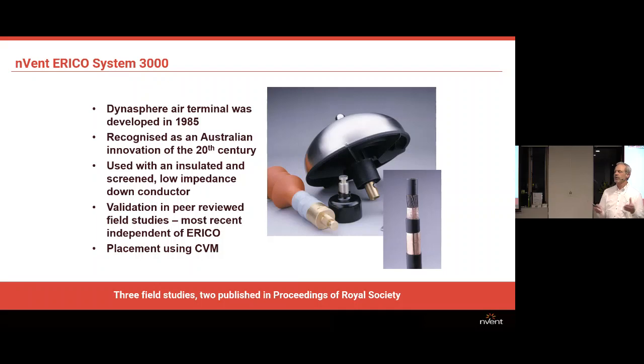The other active system is the one that has been going in for many, many years, ever since I've been representing Erico and GLT, and that's the System 3000 with the Dynasphere air terminal. It is used normally with an insulated and screened low impedance down conductor. The thing about this system is that there have been peer reviews done on it where they have studied multiple installations around the world and recorded that the performance of the system is better than what's actually claimed. So these field surveys are available for study for anybody who wants to look at them. And the collection volume method is used to place these air terminals.